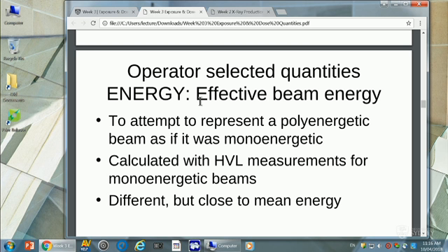what you do is you go and X-ray the dosimeter with your conditions at a particular kVp, in your X-ray room, and you find out. You may have chosen a beam, and you chose something like 65 kVp. You simply find the half value layer for your beam.